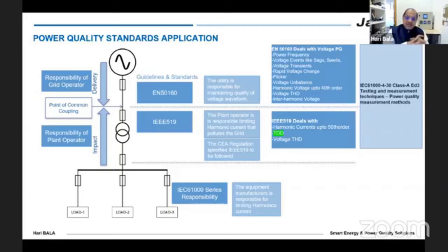Now, to do all these measurements, there is a base standard called IEC 61000-4-30. We call it Class A Edition 3, which covers testing and measurement techniques for power quality measurements. So when you want to monitor and measure power quality, there is a particular standard which tells you to use a meter which complies to the standard, which means two meters with the same configuration complying to the standard will give the same result, because measurement of harmonics by the meters or by the meter manufacturers is typically a complex process of algorithms.